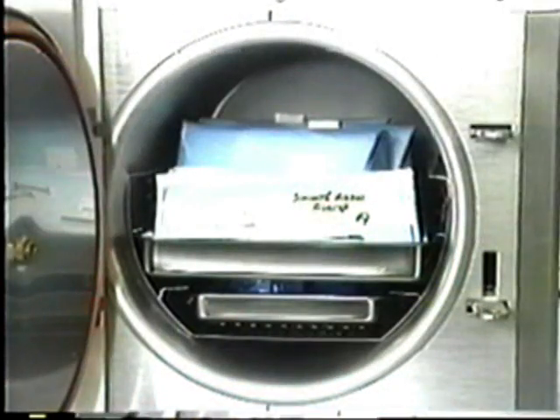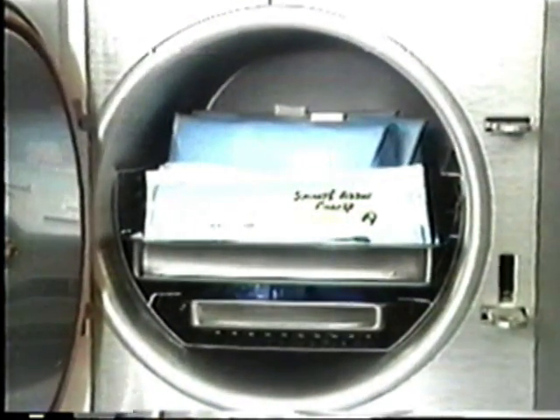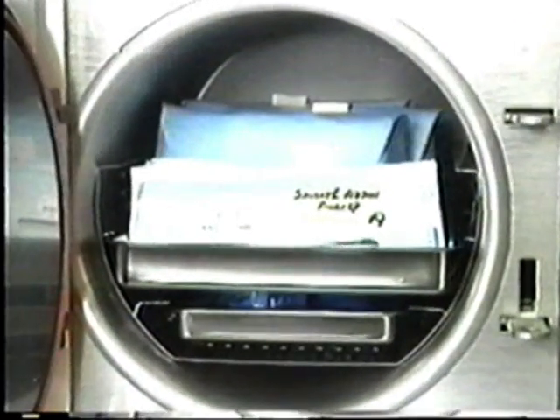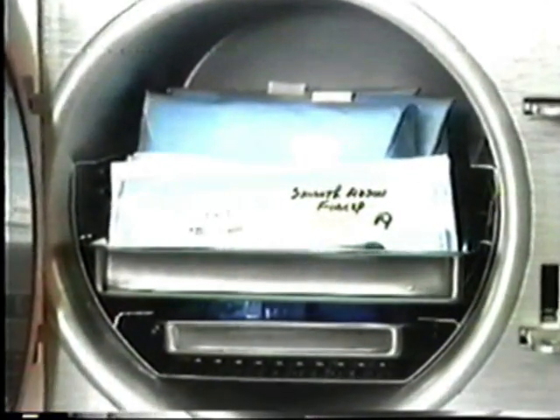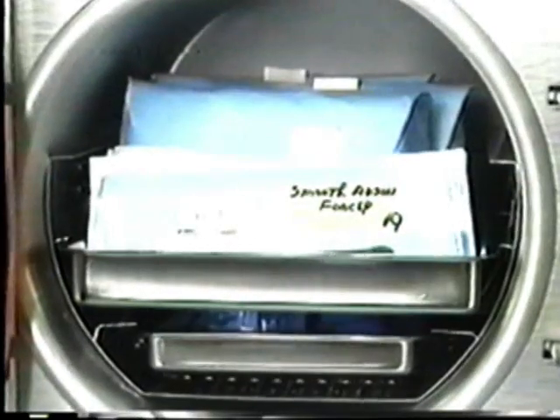Do not overload the sterilizer chamber. Place the articles as loosely as possible inside it. Leave a space between all articles and the surrounding walls in the chamber. Correct positioning and spacing of all materials will allow effective sterilization to occur when proper temperature, pressure, and time requirements are met. Failure of the indicators to change color completely denotes a serious lack of steam penetration into the pack.